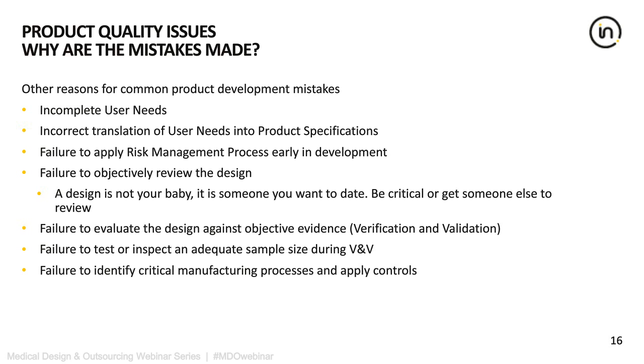And failure to identify critical manufacturing processes and apply those controls. As I mentioned earlier, when you get through verification and validation, that should include process validation. And you should know that if there's something critical to the performance of the device or the risk of the device, and it can be adulterated in the manufacturing process, that you have to apply appropriate controls to assure that the quality of the device is maintained by the manufacturing process.